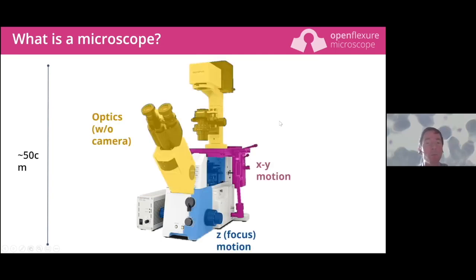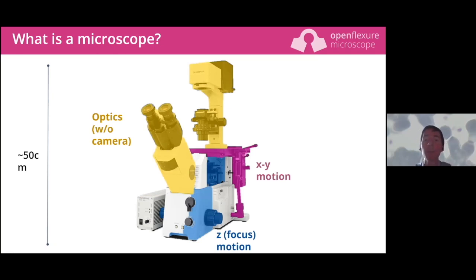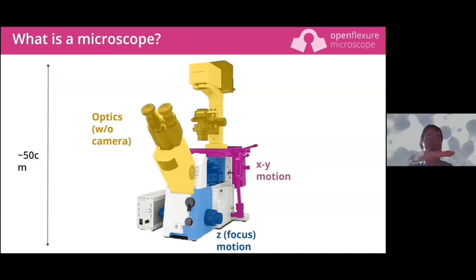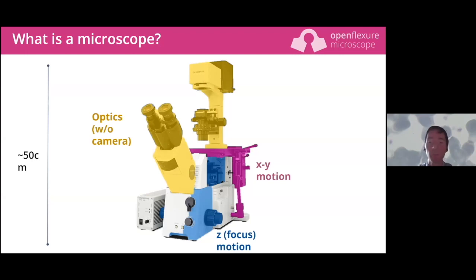So what's it made of? The optics are the obvious thing, but by weight an optical microscope is about 99% mechanics. Even by cost, the optics are a smaller proportion than you might think. A huge amount of the engineering effort goes into moving your sample around in the plane, moving it up and down to get into focus, and then keeping everything in place so your sample doesn't drift out of focus and produce useless images.